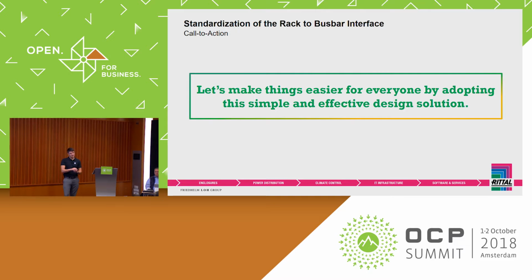What do you mean, change the shelves? So you should have been able to line up the position of the PEM nuts in the bus bar with the correct shelf if you had the bus bar in the correct position. But I suppose if you've adjusted the bus bar position in the frame, you are going to get misalignment if it's not sitting within an OU.